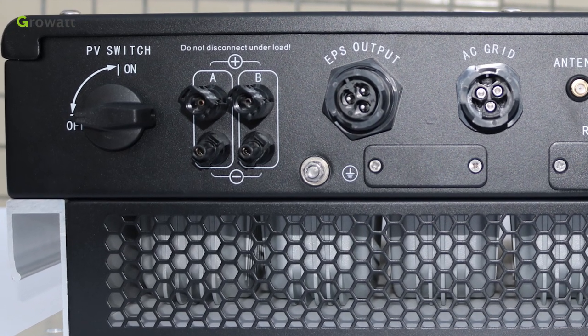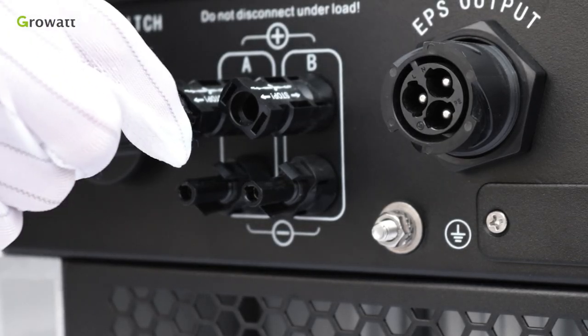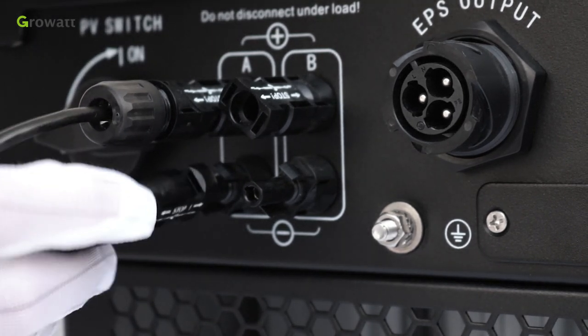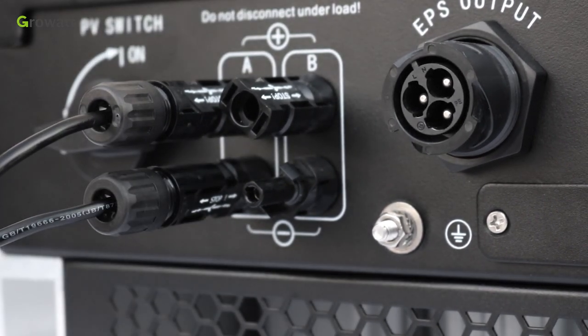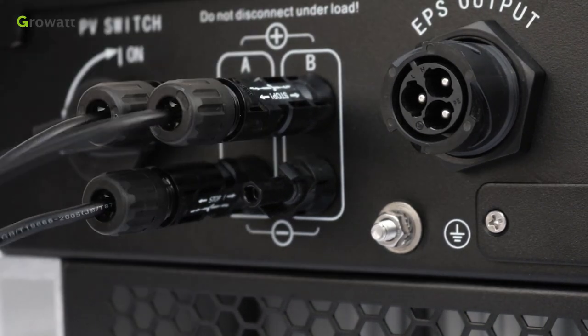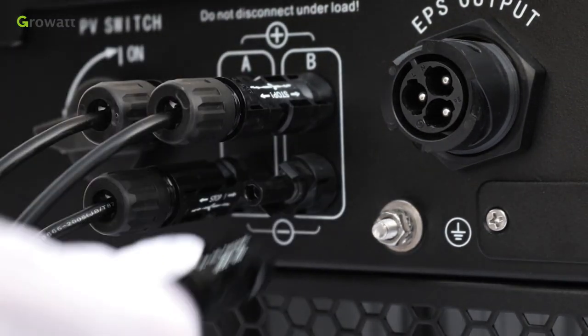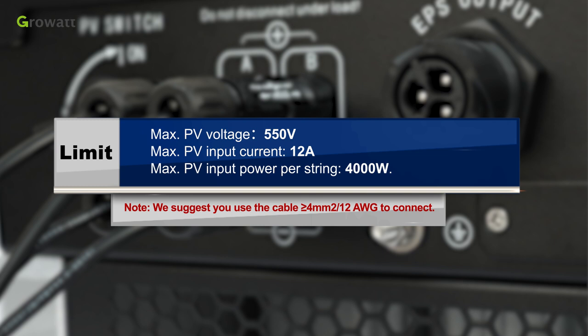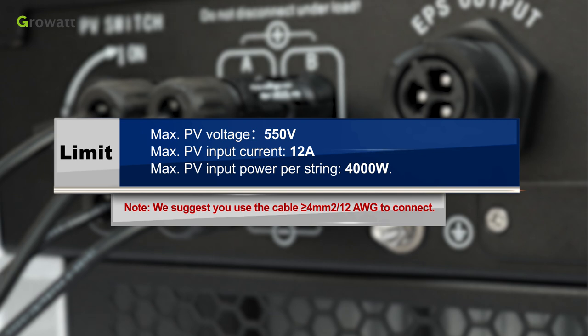1. Make sure the PV switch is off. 2. Similar to the traditional inverter, connecting the input of PV panel can be realized by using PV terminal. 3. Insert positive and negative cables of solar panel into the relative PV terminal of SPH. Limit maximum PV voltage 550 volts, maximum PV input current 12 ampere, max PV input power per string 4000 watts. Note, we suggest you use the cable which is greater than 4 square millimeters (12 AWG) to connect.